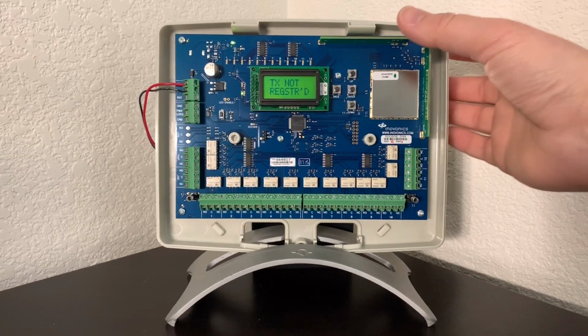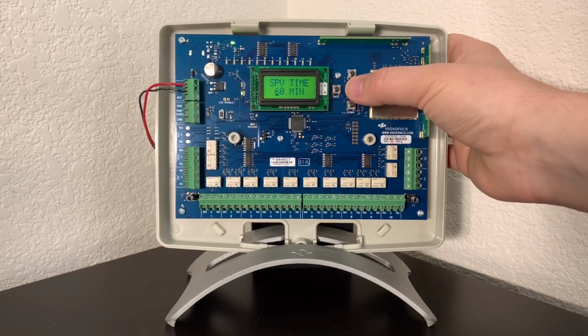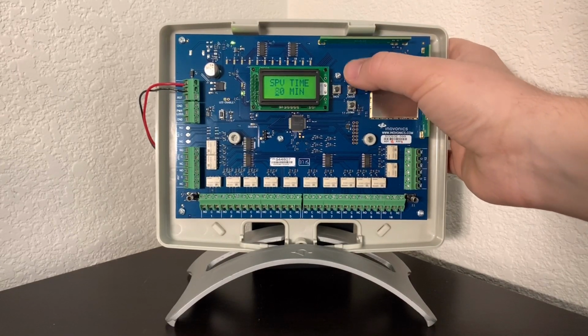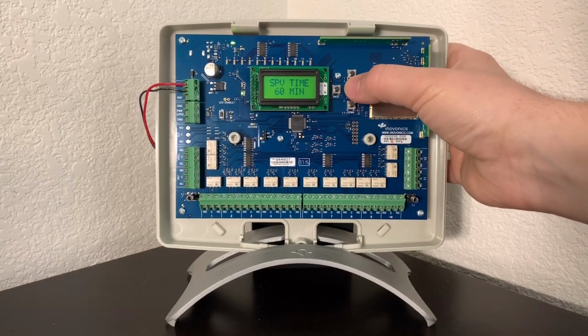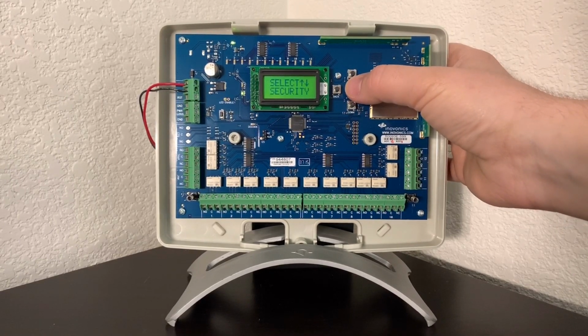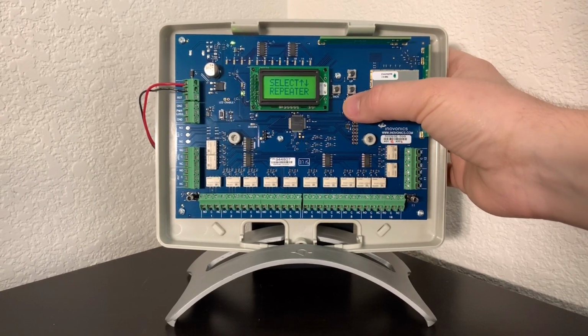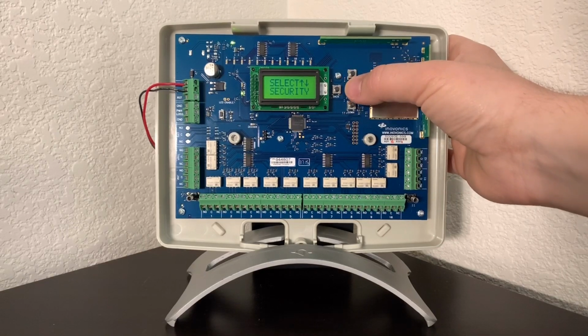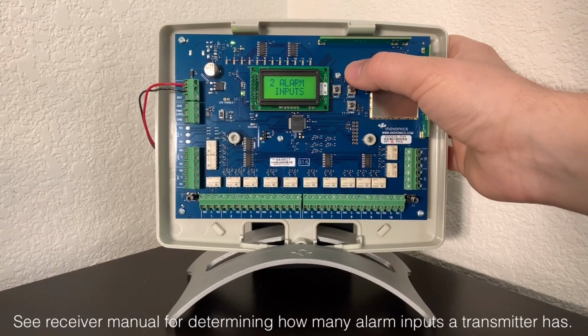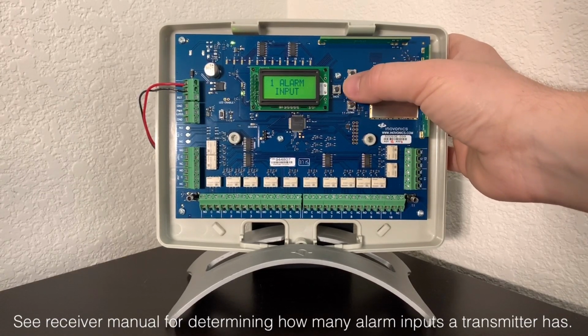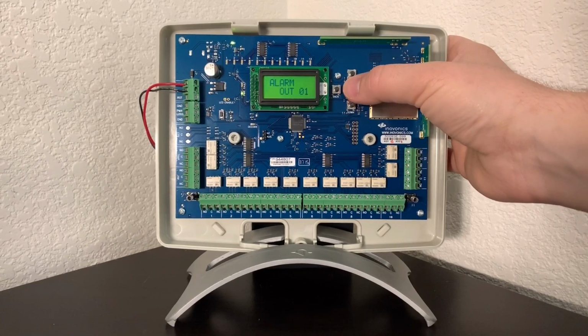We can now choose our supervision time frame. The default is set at 60 minutes. You can make this longer, but I wouldn't recommend going any shorter than 60 minutes. We'll now go between Select Security and Select Repeater. For all transmitters, we'll choose Select Security. We can now choose between 1 to 4 alarm inputs. An EN1223S is a 1-alarm input device, so we'll select that and hit Enter.